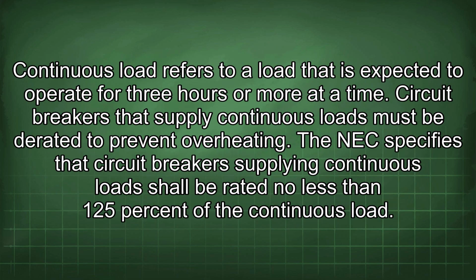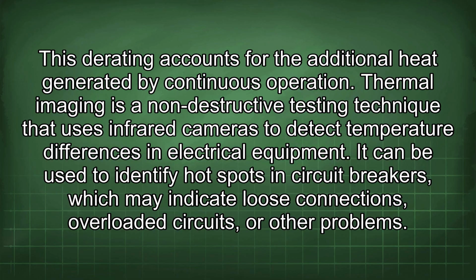Continuous load refers to a load that is expected to operate for 3 hours or more at a time. Circuit breakers that supply continuous loads must be derated to prevent overheating. The NEC specifies that circuit breakers supplying continuous load shall be rated no less than 125% of the continuous load. This derating accounts for the additional heat generated by continuous operation.